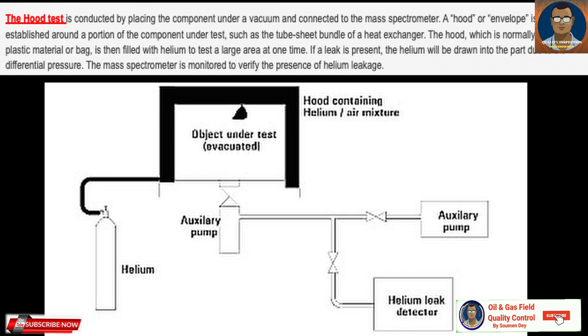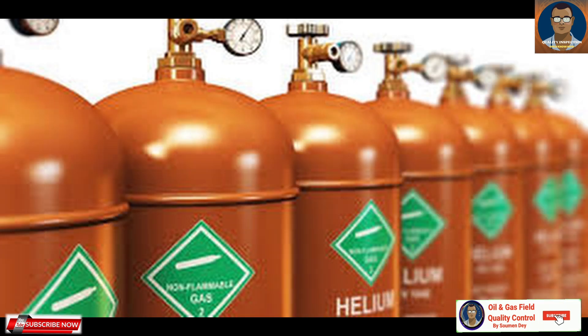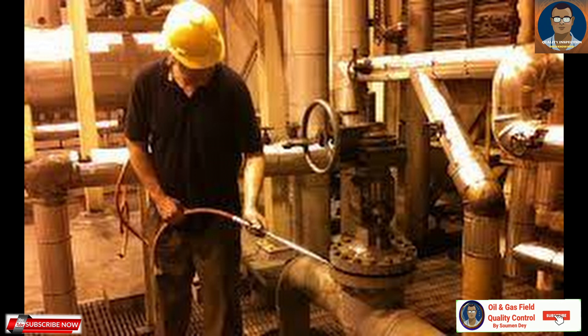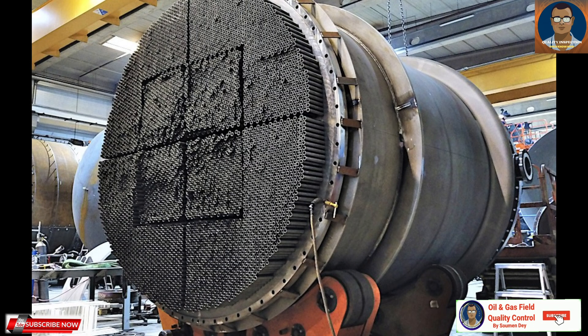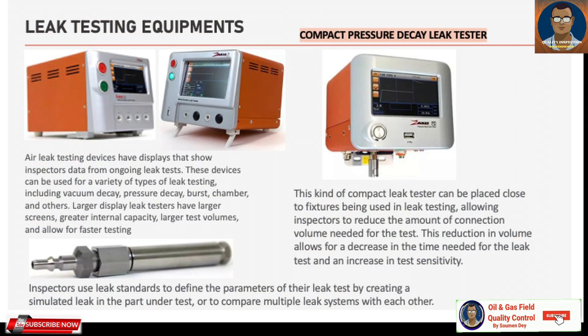The mass spectrometer is monitored to verify the presence of helium leakage. Helium leak testing and mass spectrometer testing is performed on many components in the nuclear, chemical, and aerospace industries, among others. It is imperative to ensure a component passes a helium leak test to confirm it is leak tight. Some components, such as heat exchangers, must be tested to ensure gases and/or liquids are not mixing due to a leak, which could be extremely detrimental to operations. Other components need helium leak testing to ensure they are vacuum tight, as any leak drawing air or other gases into the system could drastically and negatively impact performance.